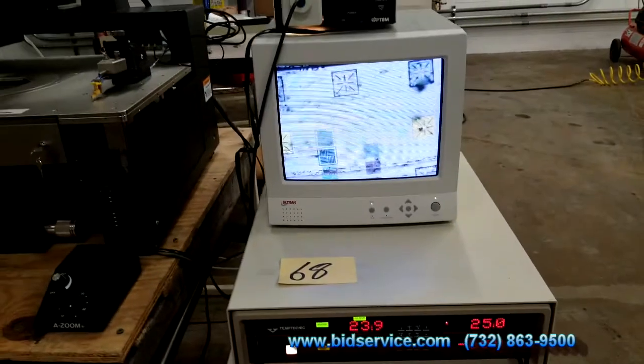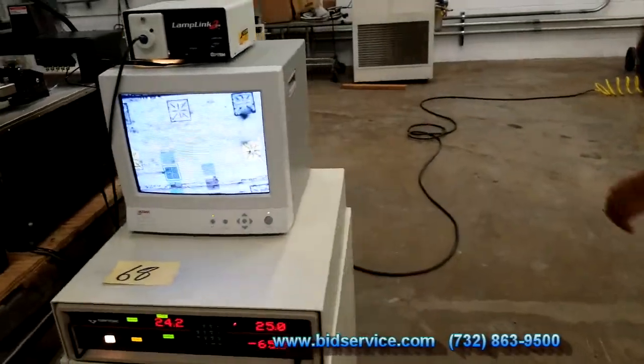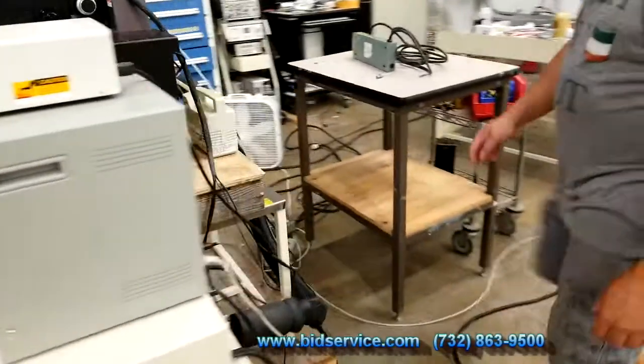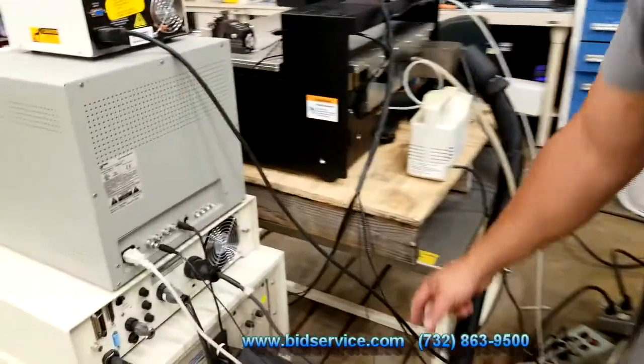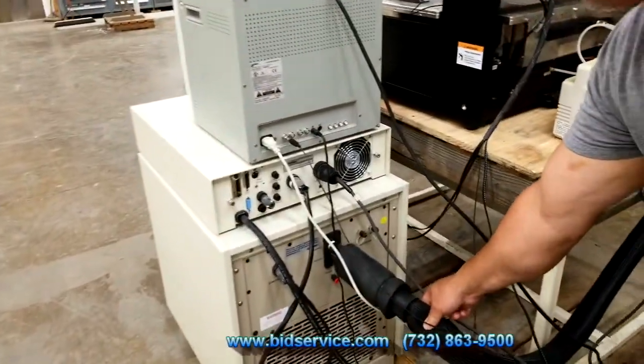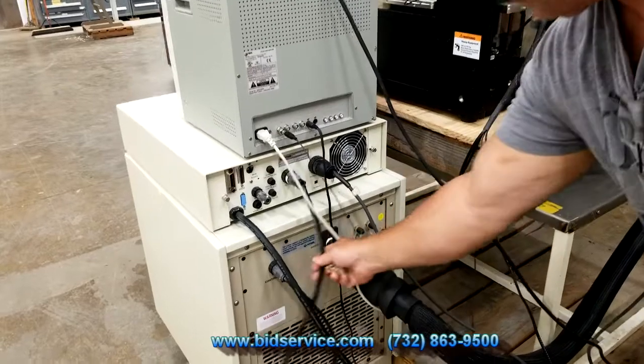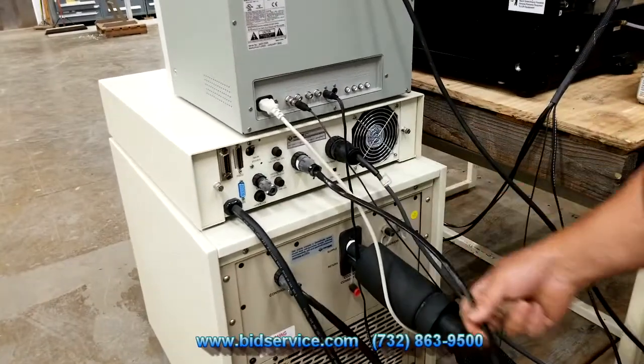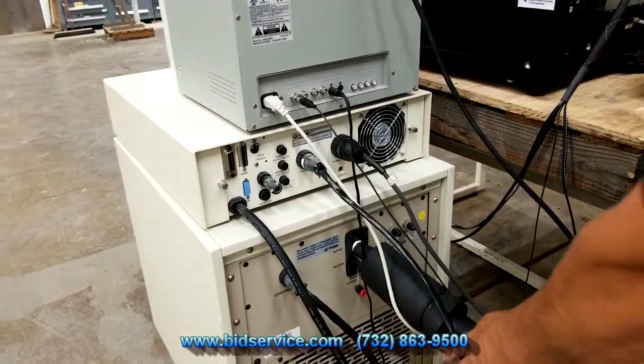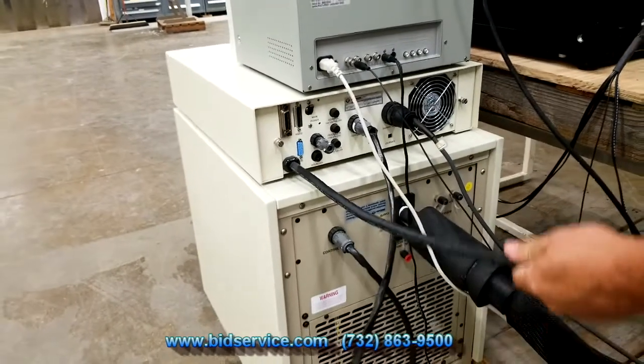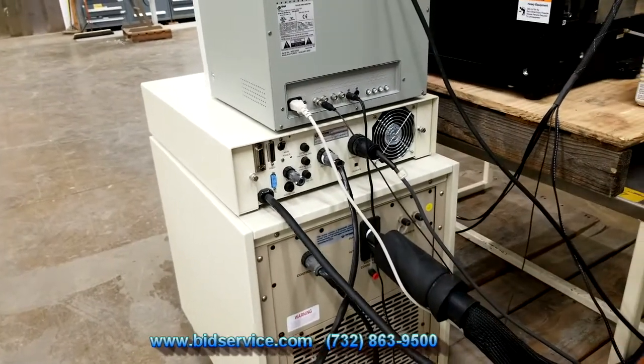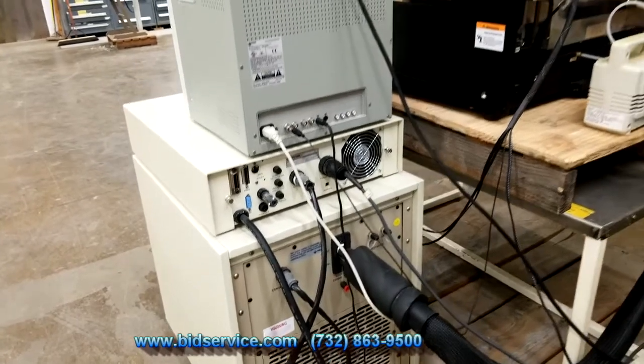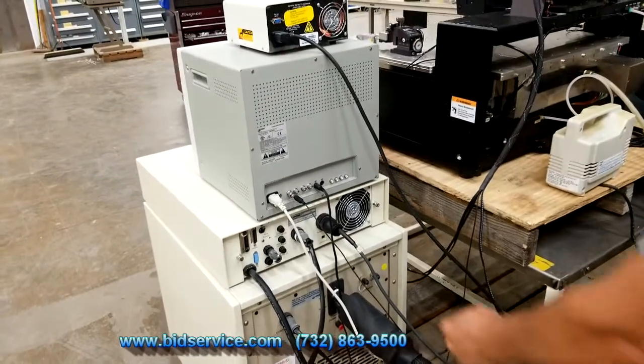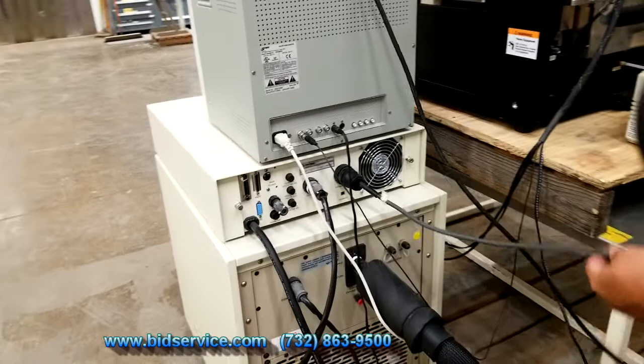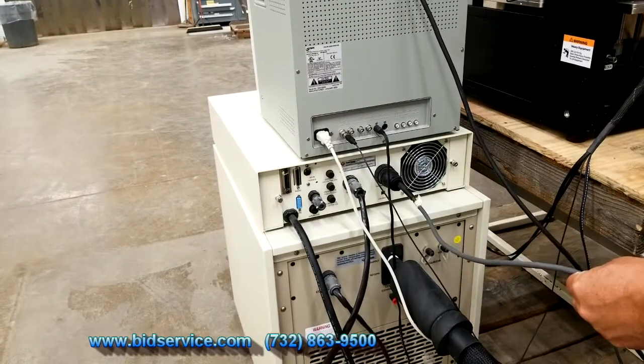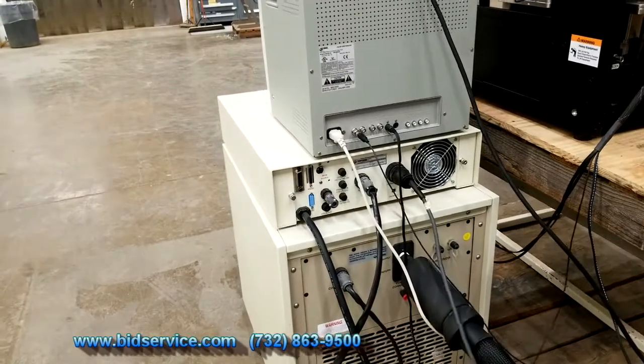Now coming back to the back of the system, you can see all the hookups here. You got your coolant lines that run from the chuck. You also got your interconnect cable between the compressor and the controller. Also heavy duty AC line voltage. It requires 110 volts at 30 amps. And then you got your line that goes to your chuck that reads the temperature and applies the heat to it.